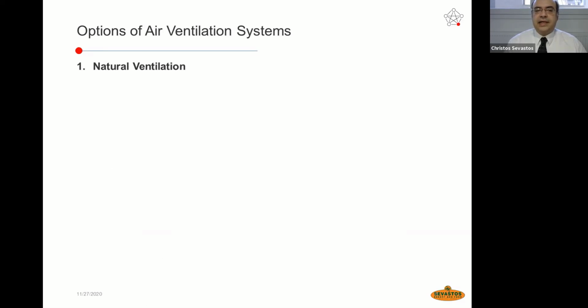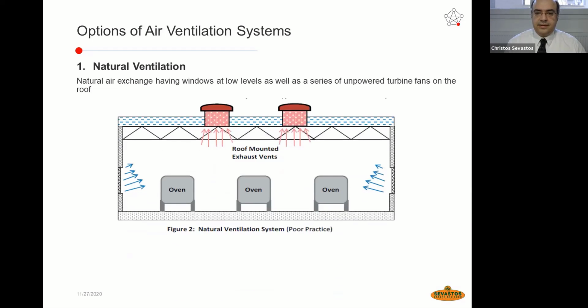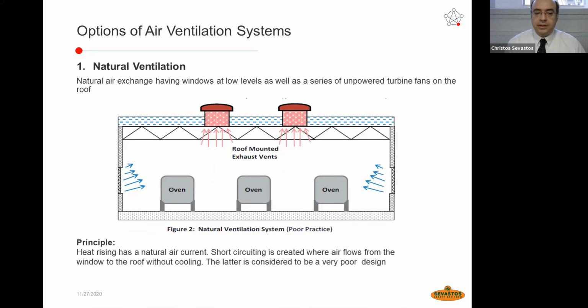Options of air ventilation. Let's go to the natural ventilation. This is the first topic regarding the air ventilation. This is a configuration that often is applied in areas where we have ovens. The principle is heat rising to the top, and we are going to have air ventilation from the windows. So we are going to have roof-mounted exhaust vents, and this is a very poor design because air supply is happening from the windows, and from the roof we are extracting the heat without applying the proper air supply inside the oven room. This is the natural ventilation, and this is a very poor design.